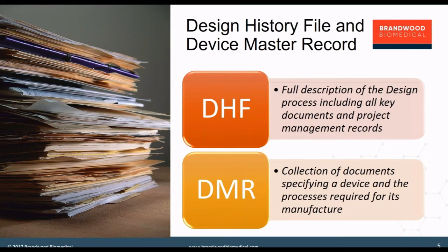The DMR is the other concept here. The DMR is the device master record. This is essentially a snapshot of the current information that is required to produce the product within its current specifications. So that's the collection of documents specifying a device, as well as the processes which are required to manufacture the product.